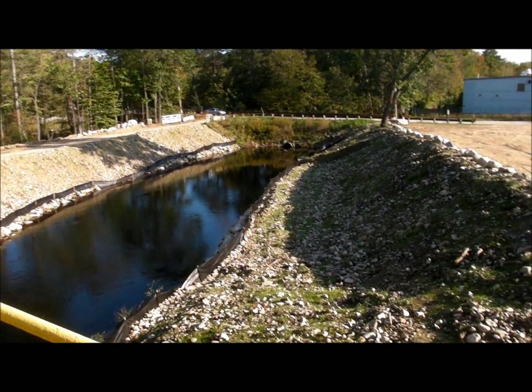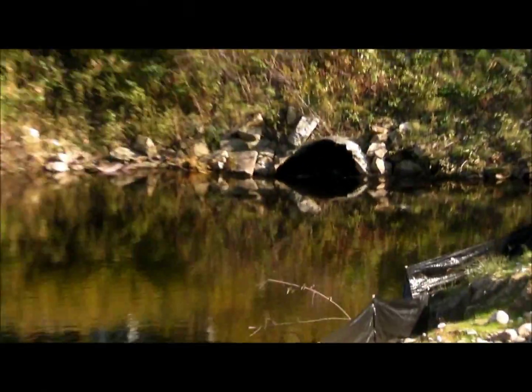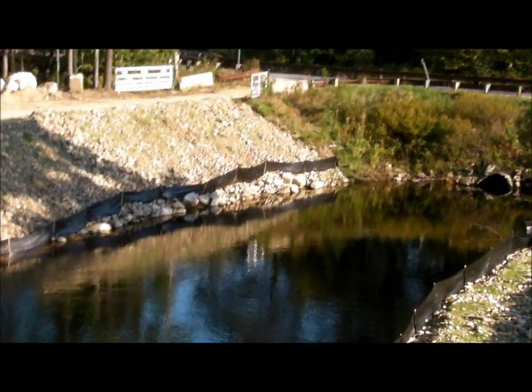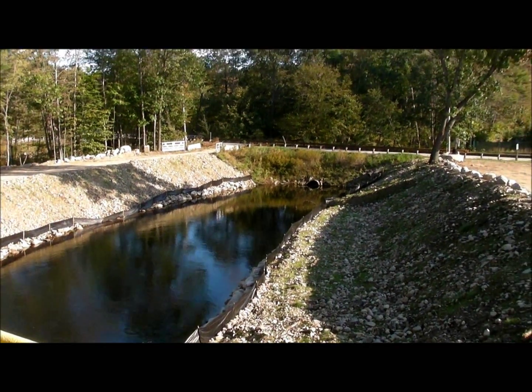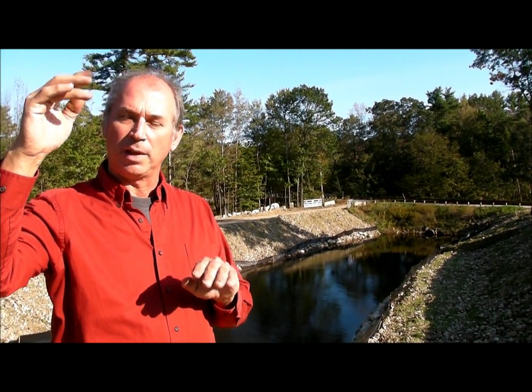There's a road going across there — that's Spalding Avenue. Originally that was a full bridge, and in the 70s when that road was redone, they took out the bridge and replaced it with a small culvert. That culvert is causing the tailrace to back up, making the water come 3 feet higher than it should be. When you generate power, it's the difference between inlet and outlet, or head pressure. The design is for 25 feet, but we're getting about 22 feet. That 3-foot difference in pressure is about 17% of our electricity capacity, so instead of 300 kilowatts, we can only generate 250 to 260, depending on what the water level is in the river.